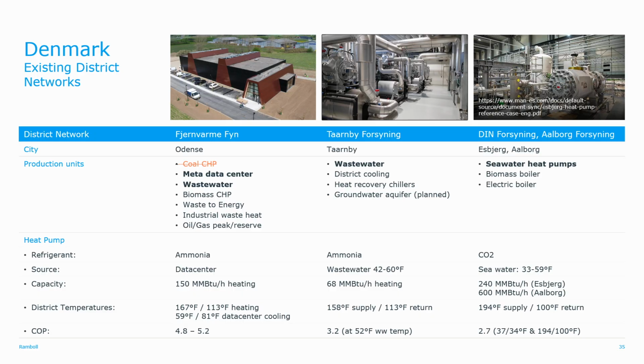These are all existing districts. Denmark over the years has transformed from steam-based district heating to lower temperature hot water networks, and now they're implementing heat pumps more readily into their systems. In one city there's a data center, and they're recovering waste heat from that data center. They also have a wastewater treatment plant there, utilizing the effluent as a heat source for heat pumps, but there's also quite a bit of biomass CHP, some waste energy, industrial waste heat that they're using, and then also combining that with some oil and gas peaking and reserve capacity.